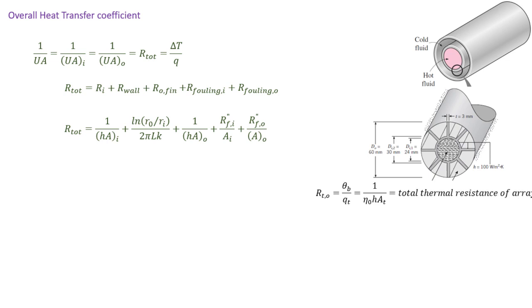So remember the total thermal resistance of an array can be related to the efficiency of an array. So we can incorporate the efficiency of the fins on the outer or the cold side. Do note that there's an array efficiency for the convective resistance on the cold side, as well as the fouling factor on the cold side, since there would be fouling on the fins as well.